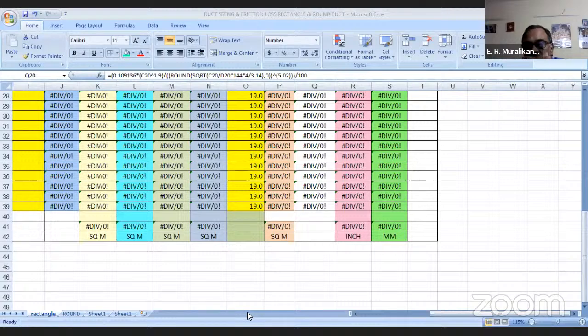Now, for fire-rated ducts, you're going to have a very high cyclonic effect to pull all the smoke. So that's why at the start I explained the configuration of rectangle duct, round duct, and elliptical duct. Whenever you go for a dedicated smoke duct, go for round ducts only with high velocity, maybe around 1600 fpm or so. Only then will a high Venturi effect be created and high vacuum be created to expel the air very fast.